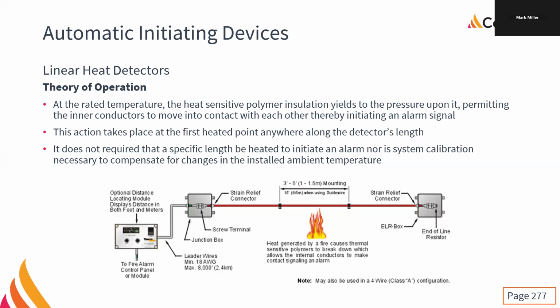There's all sorts of different ways of mounting it, but we have to be careful that we do install it properly. And it will trigger anywhere along its length, which is fantastic because we can get a very large amount of coverage. And usually we don't really care where along its length it's activated. We just want to know that it is activated. And that's enough. So we use the much cheaper module and attach it to the fire alarm control panel.